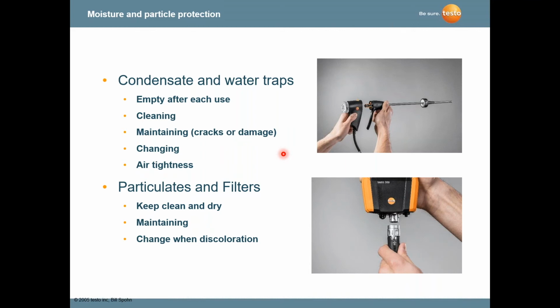Our filter is in the probe assembly, a white or yellow filter, and it turns black from the inside out. So if you have a black filter, it's time to change it. Oil has more particulates than gas, so you may be changing the filter more frequently with oil. The quick disconnect allows you to connect the instrument with one probe. Internally in this probe attachment are a thermocouple connection, the flue gas hose, and the draft hose. They're separate hoses.